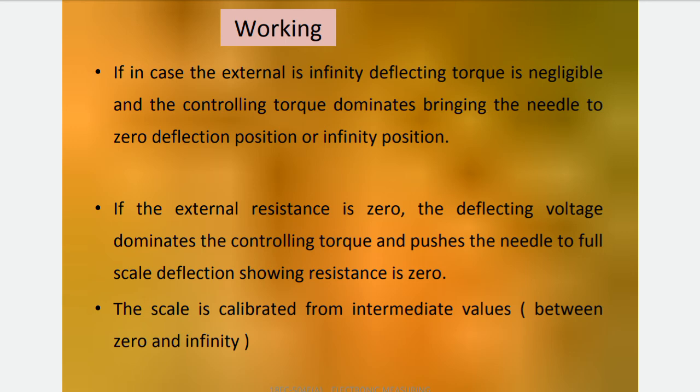They are also designed to measure a resistance of only a few ohms, such as the resistance of ground of tower footings or ground wires. The Megger is mainly used for measuring the insulation resistance of cables, insulators, and windings of motors and generators.